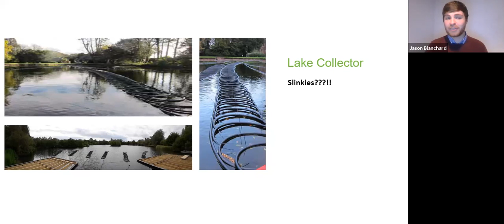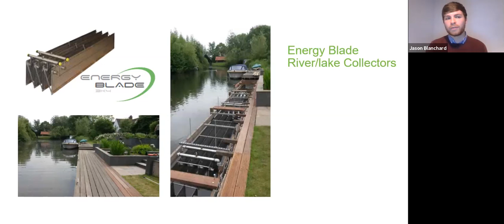Now, a more recent development and newer technology are energy blades. They've come into the market in the last 4 or 5 years, I believe. They are effectively plate heat exchangers or radiators running in reverse, taking energy out of the water as it passes through them. There are no moving parts, and they provide that energy back to the heat pump. As you can see here, you can install them along a riverbank, cover them with decking, and you'll never even notice they're there. So this is quite a neat solution if there is running water present.